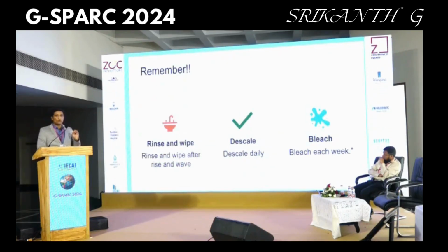I'd like to put it in a more, see, when we try to teach our HCPs, our staff, it is always better to use rhyming or rhythmic sentences so that they remember. So what we teach them is to rinse and wipe after every rise and wave. When the patient rises and waves you by, you have to rinse. That is rinse the machine, that is the heat disinfection of the machine, as well as wipe the surfaces. Descale daily.